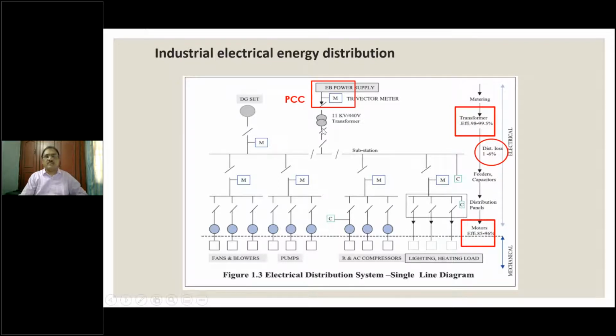It is not the transformer secondary, or anywhere inside the network. It is exactly at the point where the EB power supply and the trivector meter provided for that facility meet. That is where the vacuum circuit breaker is, that is where the point of common coupling is. And the distribution losses and transformer losses are given here as a number.